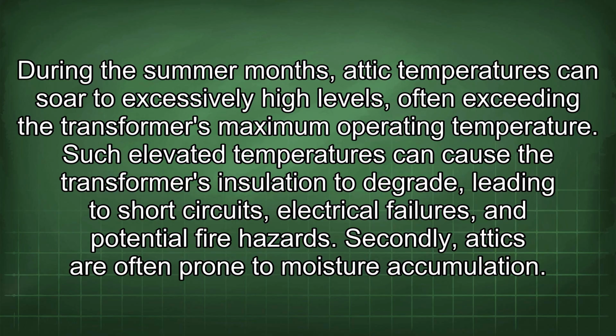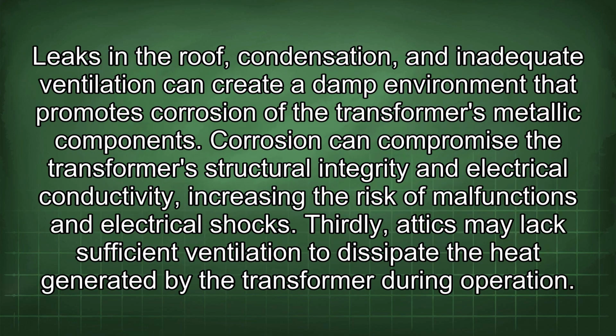Secondly, attics are often prone to moisture accumulation. Leaks in the roof, condensation, and inadequate ventilation can create a damp environment that promotes corrosion of the transformer's metallic components. Corrosion can compromise the transformer's structural integrity and electrical conductivity, increasing the risk of malfunctions and electrical shocks.